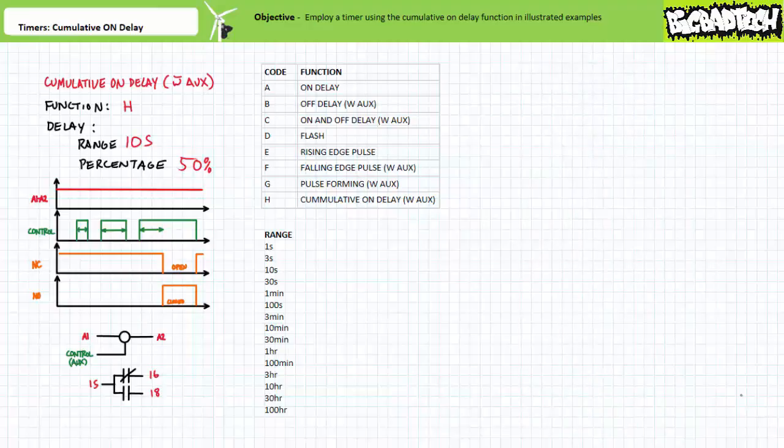Troubleshooters take note. A multifunction timer executing the right function at the wrong time needs to have the delay adjusted. In contrast, a multifunction timer executing the wrong function at the right time needs to have the function adjusted. I'd like to say that the misinterpretation of functions is a rare occurrence, but it isn't, and you need to be aware of this possibility.